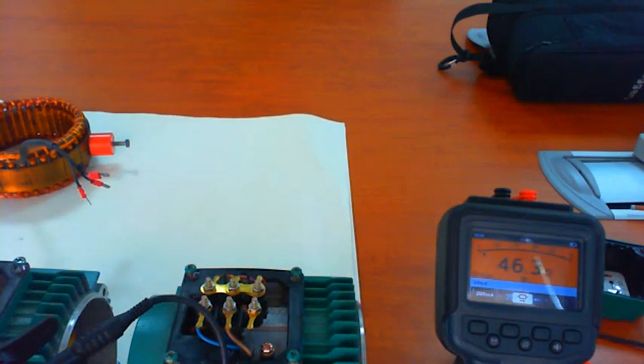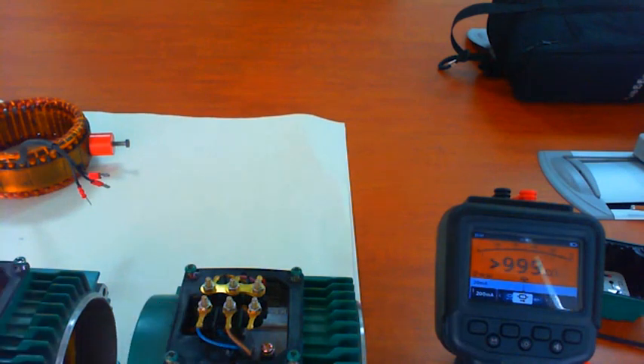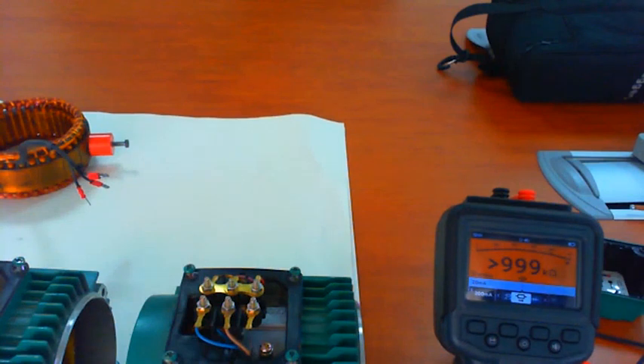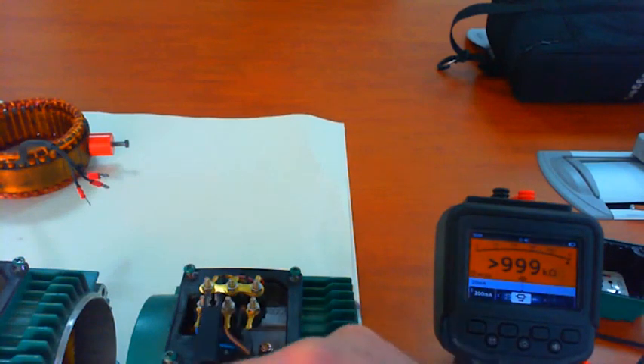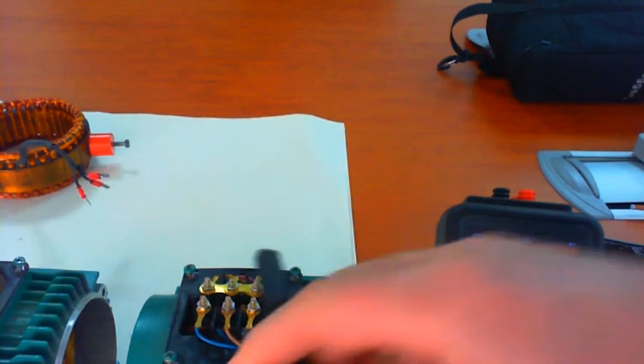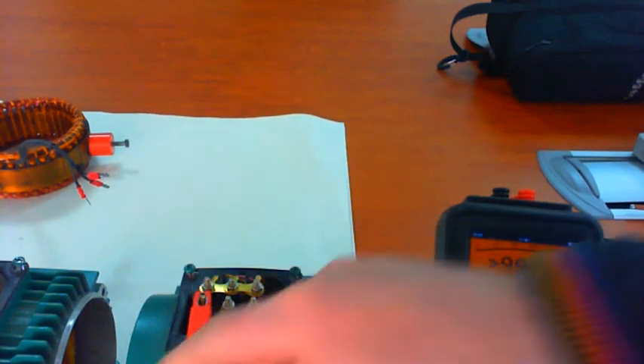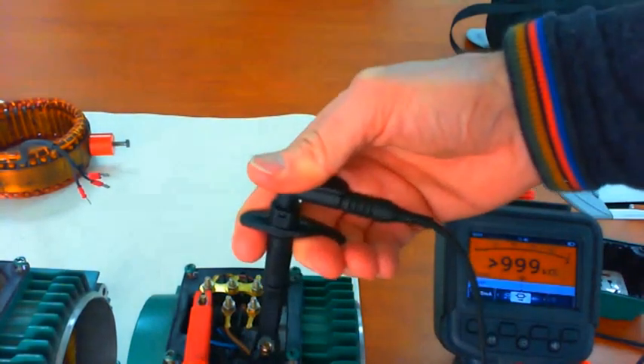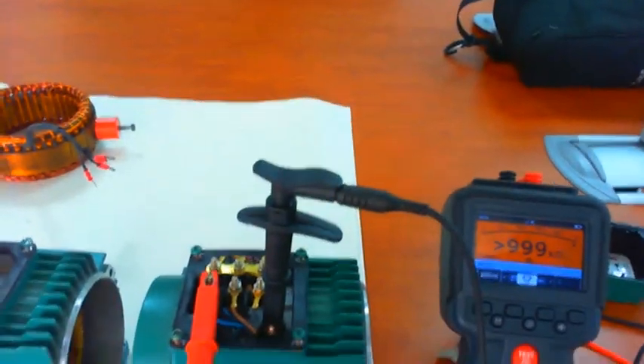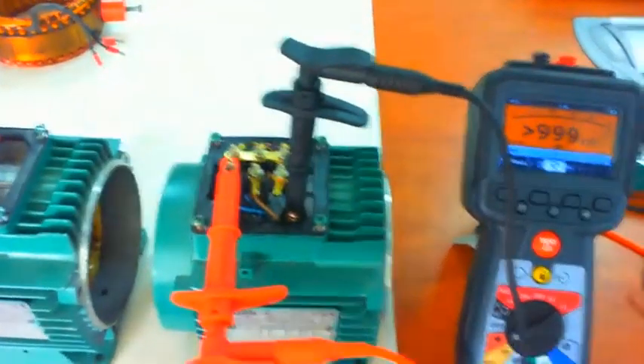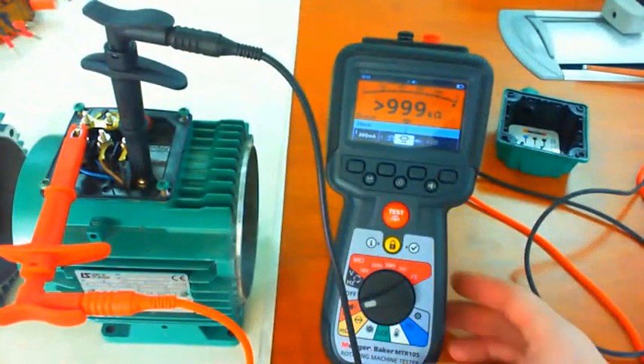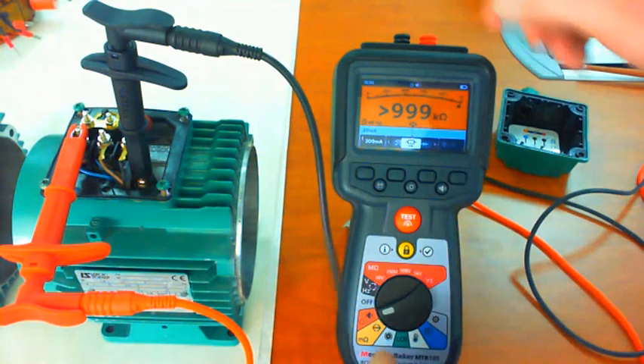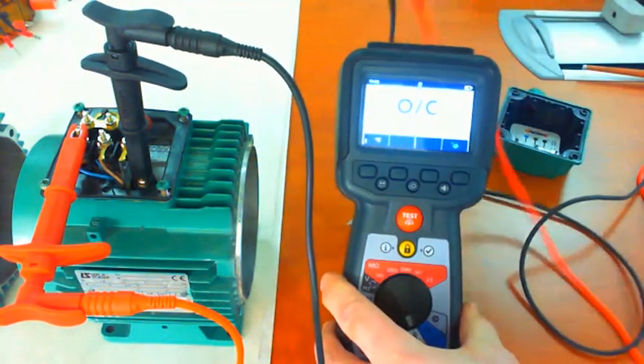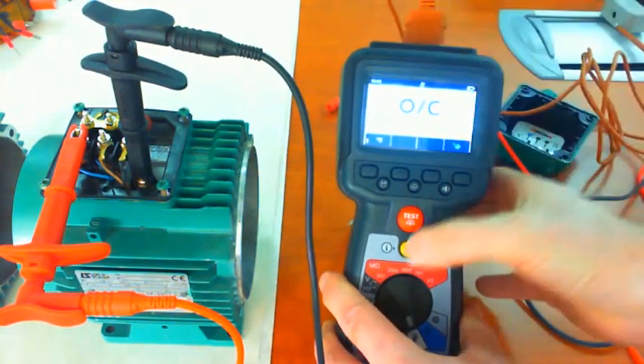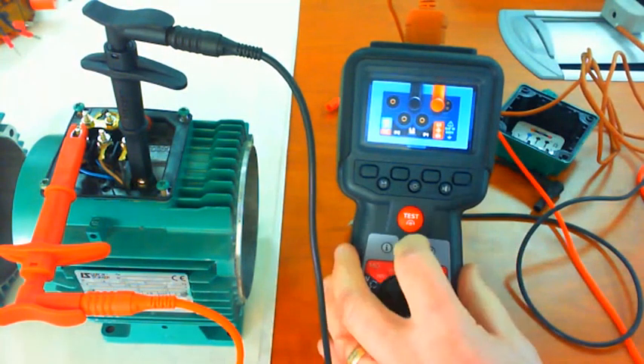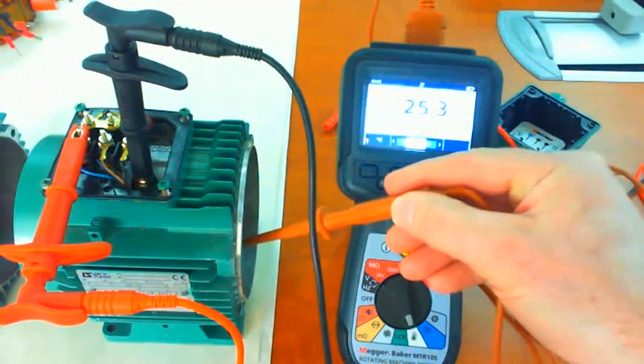Okay, so what we want to do now is an IR test. So we can use the same motor. So we put one live lead onto the winding, which is star connected. We'll put the ground lead onto the earth point. There you go. And what we want to do first is we actually want to measure temperature, don't we? So if we go round to the temperature setting and we'll plug in the temperature probe. If we're not sure how to do it, it tells us how to do it. We're going to measure now the winding temperature using the probe.